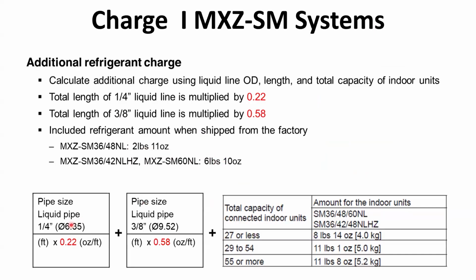So as you do your calculations right here, your 1/4 inch total, your 3/8 total, and then you get to your total capacity, what you're noticing here is you're gonna have to add more refrigerant, is what I see. The additional amount is more because the factory charge is less in these units. So that's the only thing that has changed on that. So still do it the same way, you know, install manual has this calculation.